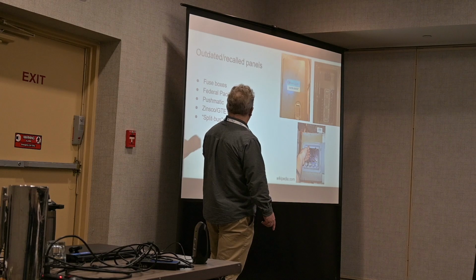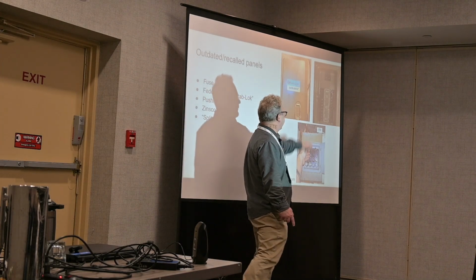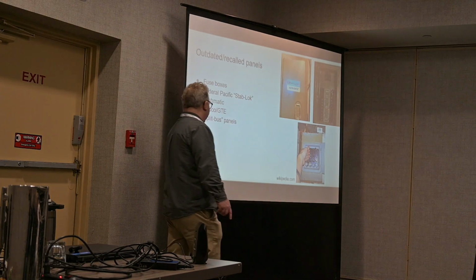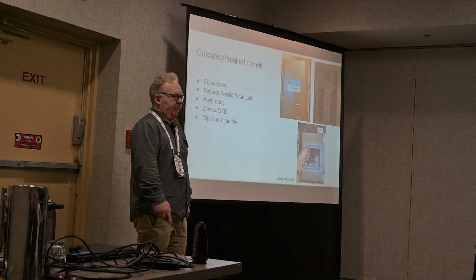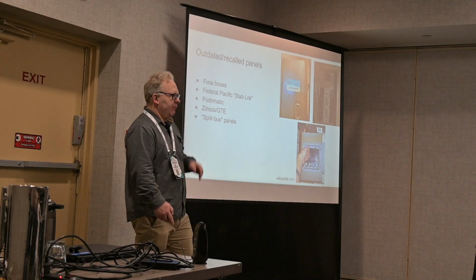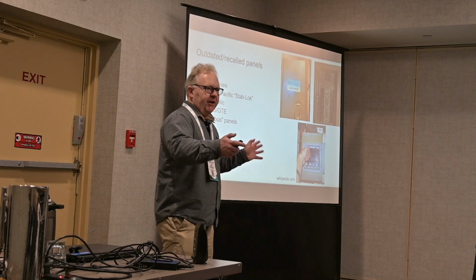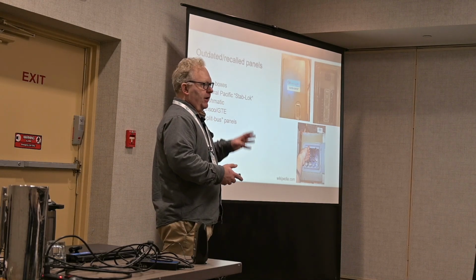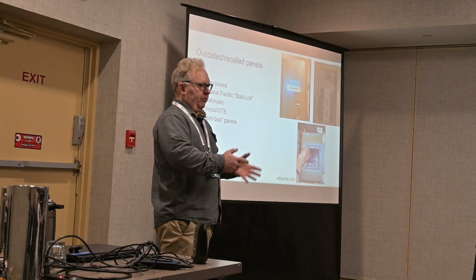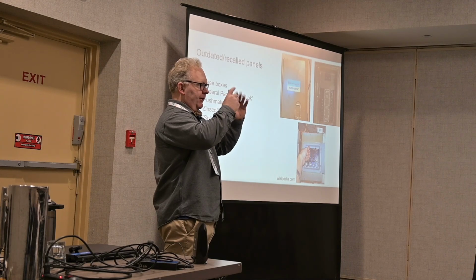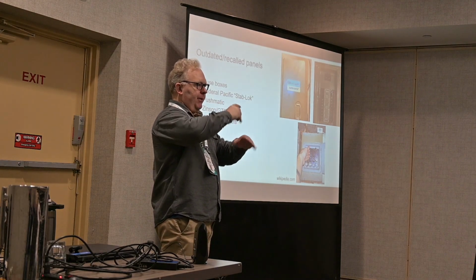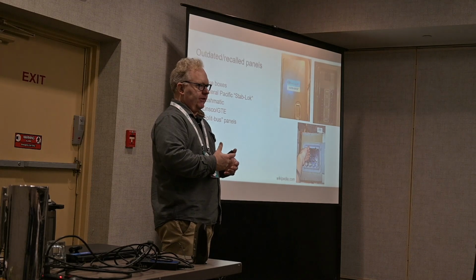Pushmatic is one, Federal Pacific, Stab-Lok is another. And there are also these split bus panels that you'll run into occasionally. You'll be able to recognize the split bus panel, and I apologize I don't have a picture, because all the double pole circuits will be clustered together in one part of the panel, and then there's going to be a gap, and then you've got all your single pole circuits.